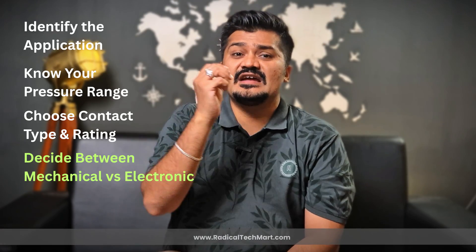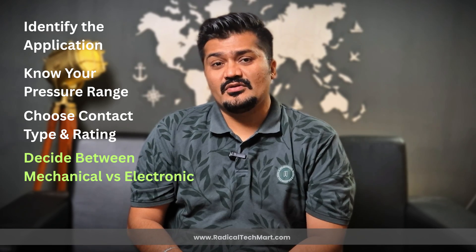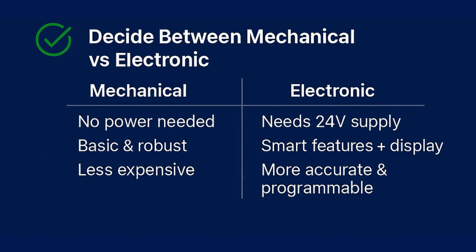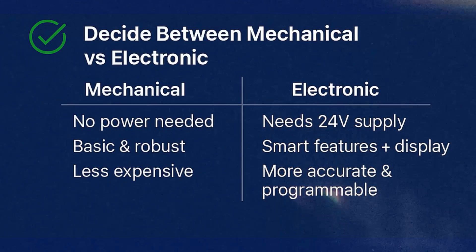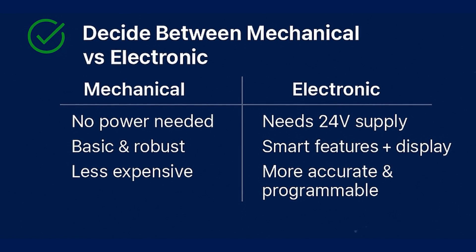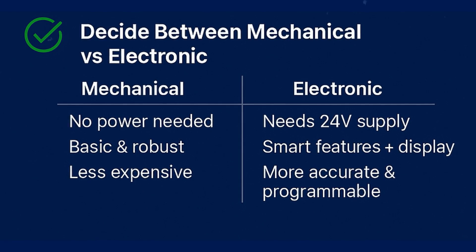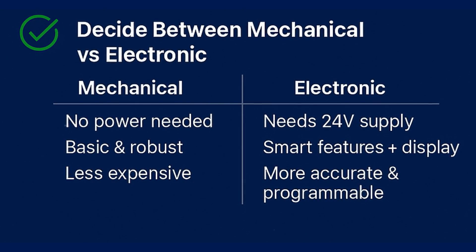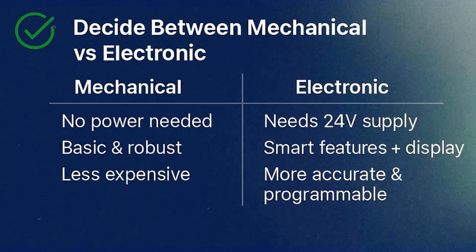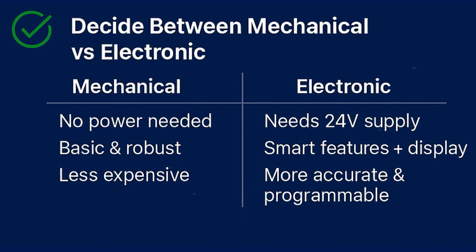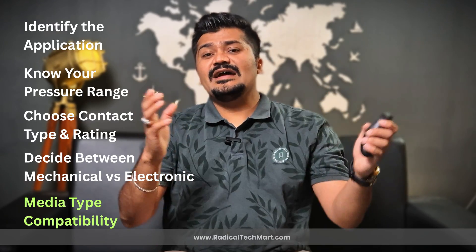Step four: decide between a mechanical or electronic pressure switch. For a mechanical switch, no power supply is needed, while an electronic switch needs a 24V supply. Mechanical is basic and robust; electronic has smart features. Mechanical is less expensive, while electronic is more accurate and programmable.